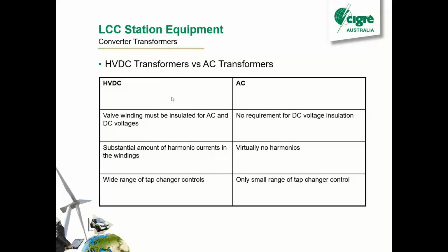Another point to note is what's different between HVDC transformers and AC transformers. The converter transformers are special. They're not just like a normal AC transformer. They have a lot more insulation in them, usually in the form of paper. So in an HVDC transformer, you have a lot more paper than what you'd find in an AC transformer, and that's due to the DC voltage stress. On an LCC HVDC, your valve windings must be insulated for AC and the DC as well, so you have to add extra paper in there. And they also have to deal with the harmonics. We saw those harmonics going into the converter, and that's going through the transformer, so you've got to deal with that.